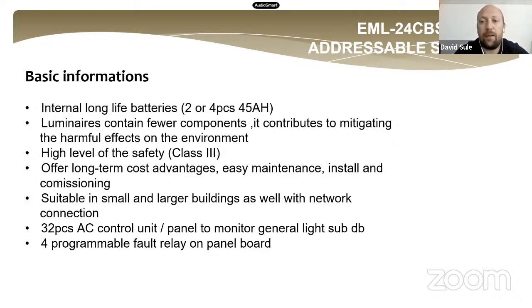The panels can be connected to each other through the local area network, which has a limit of 100 meters per active device. But the panel has another connection. It's an RS485 ring network, which is very similar to fire alarm panels. All the panels can connect to the next two neighbors, and 32 panels can be connected to the RS485 network. And we can set up one main panel, and the other ones will be slave panels.